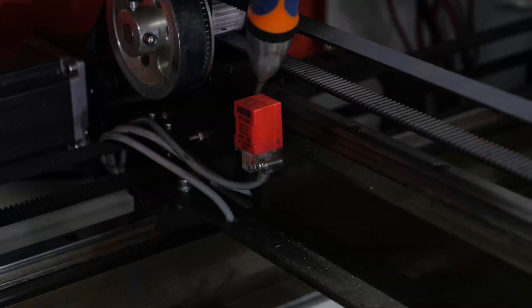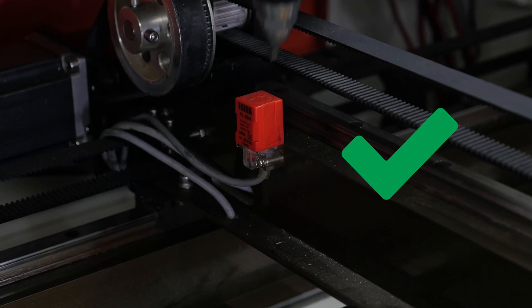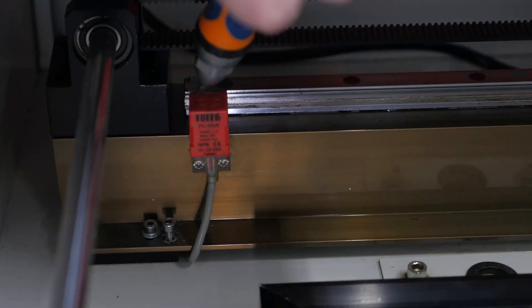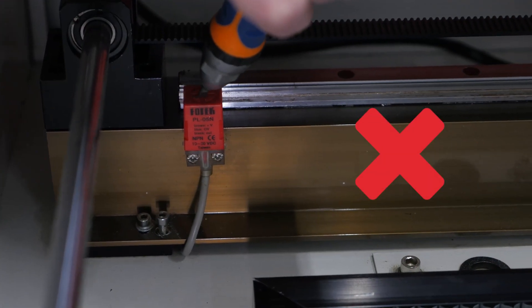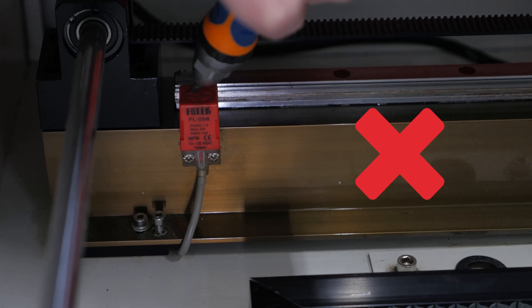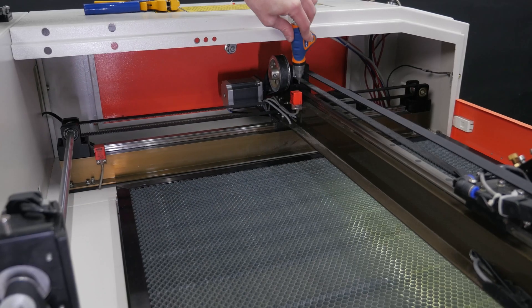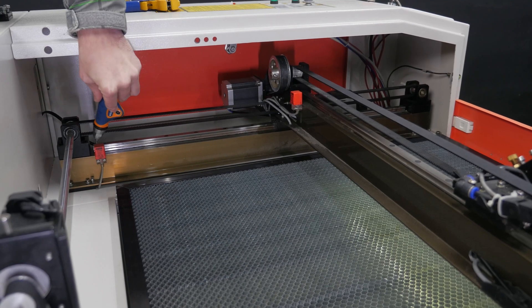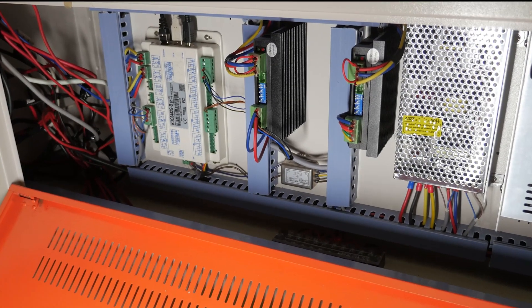The first thing to do is to check that the end sensors are working properly by holding a metal screwdriver against them. One sensor lights up, the other does not. Let us check if the sensor works by replacing it.